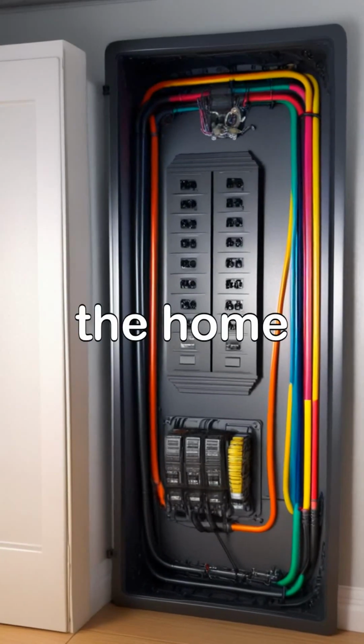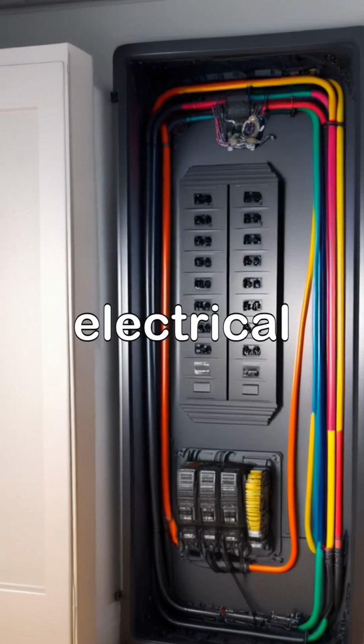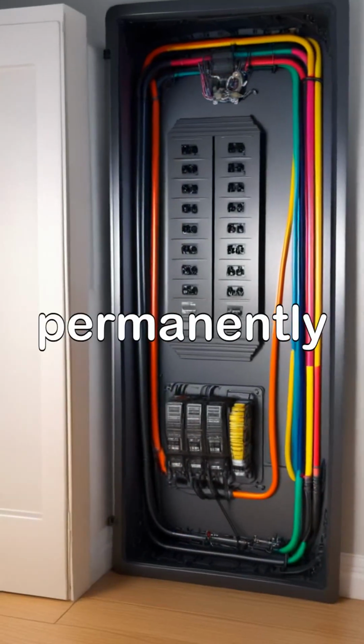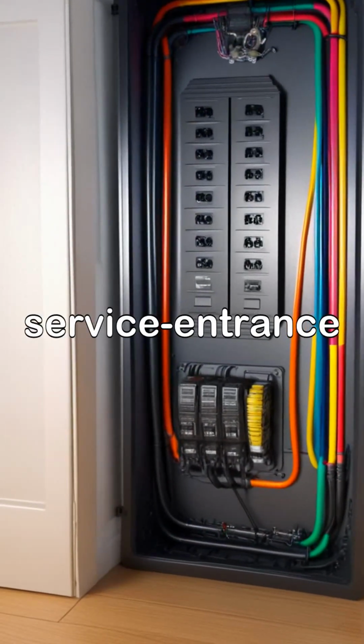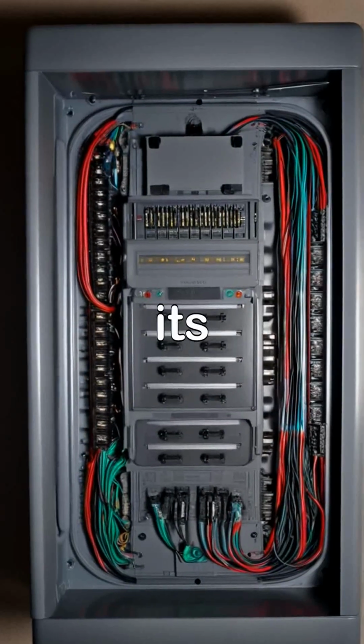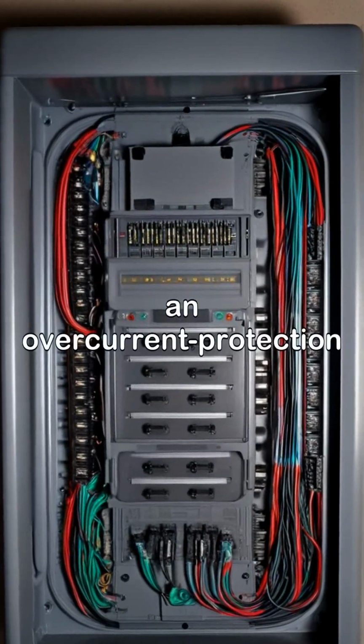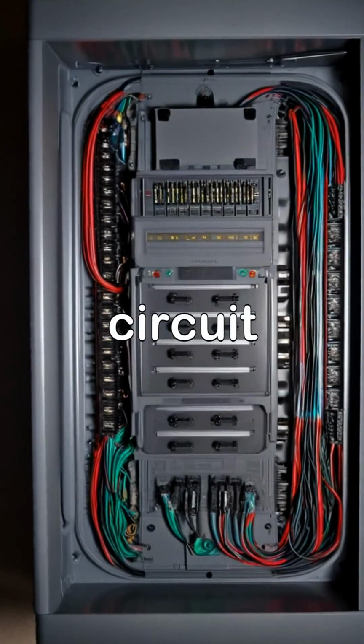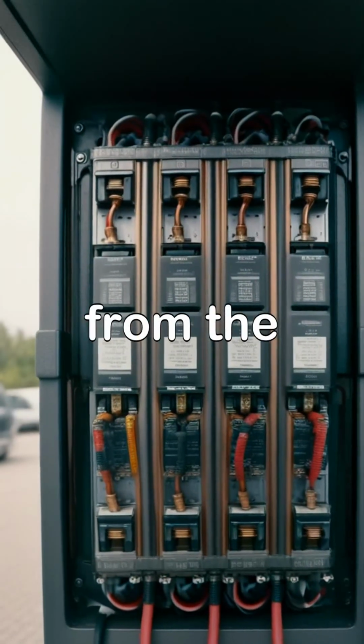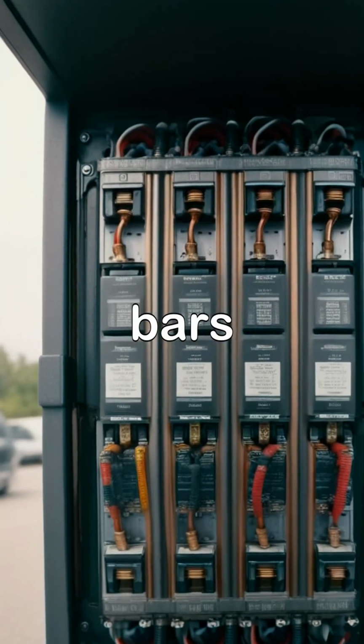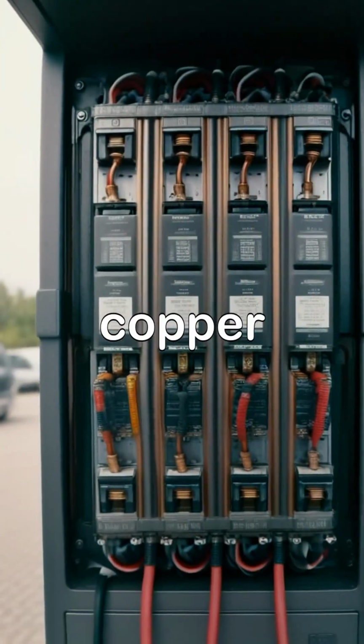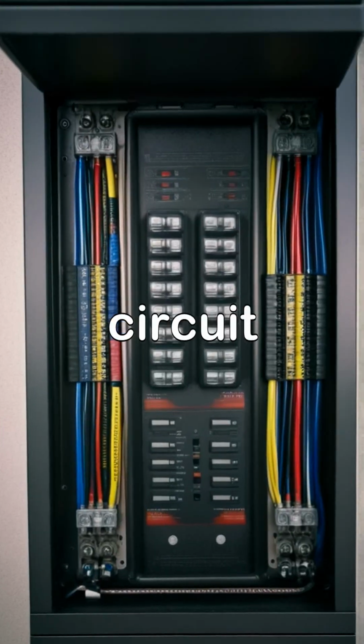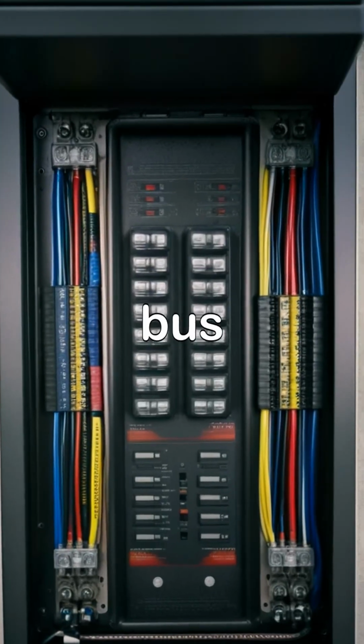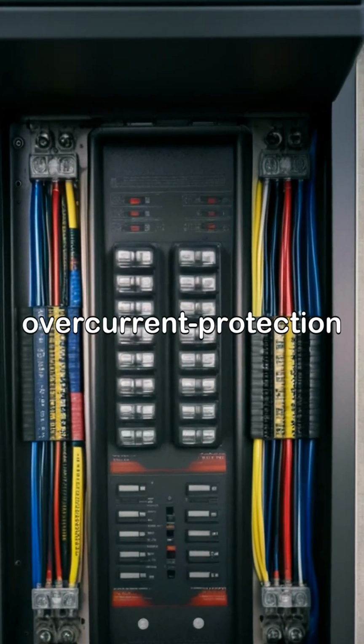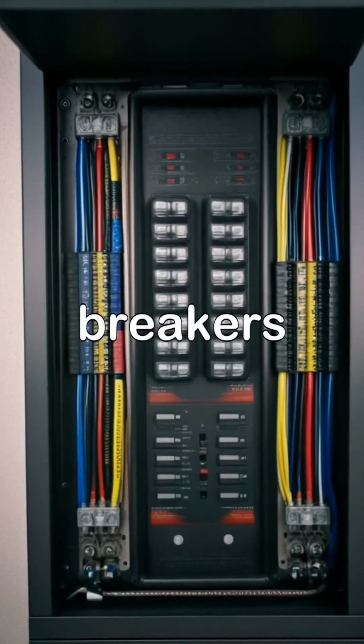Branch circuits within the home are formed by the wiring that connects electrical outlets, receptacles, and permanently connected appliances to the service entrance panel. Each individual circuit has its own hot wire and neutral wire as well as an overcurrent protection device capable of turning off power to the individual branch circuit. In the panel, 2 hot wires from the main circuit breaker energize 2 bus bars constructed of heavy metal, usually copper or aluminum. Each branch circuit is connected to one or both of these hot bus bars via individual overcurrent protection devices, either circuit breakers or fuses.